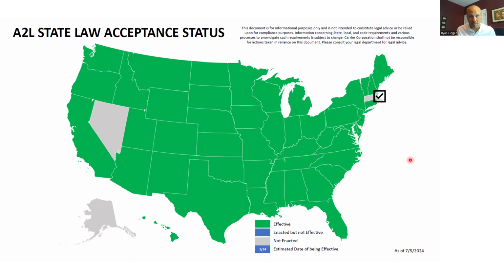So whoever makes this map, they're looking at most of the state, right? In some places like Wisconsin, there's a statewide mechanical code. So it's either they have A2L rules or they don't have A2L rules, right? But in Illinois and Indiana, where a lot of you are from, it's home rule. Every municipality makes their own mechanical codes. So some towns may have A2Ls allowed for, some may not. For example, the city of Chicago, the largest municipality in the Midwest, does not have any allowance for A2Ls.